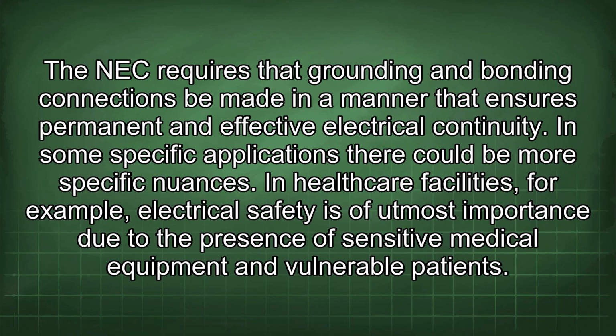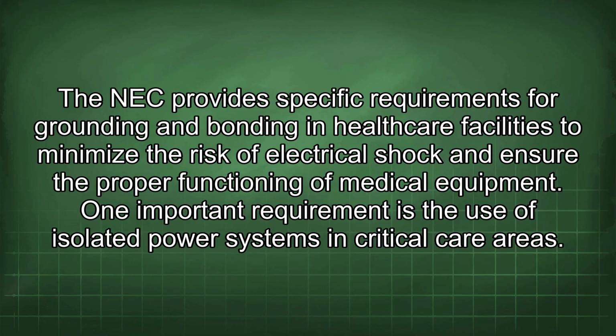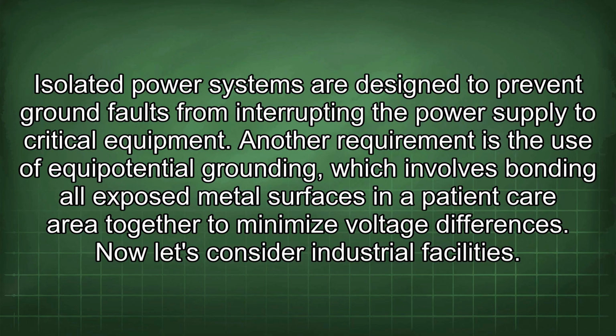In healthcare facilities, for example, electrical safety is of utmost importance due to the presence of sensitive medical equipment and vulnerable patients. The NEC provides specific requirements for grounding and bonding in healthcare facilities to minimize the risk of electrical shock and ensure the proper functioning of medical equipment. One important requirement is the use of isolated power systems in critical care areas. Isolated power systems are designed to prevent ground faults from interrupting the power supply to critical equipment. Another requirement is the use of equipotential grounding, which involves bonding all exposed metal surfaces in a patient care area together to minimize voltage differences.